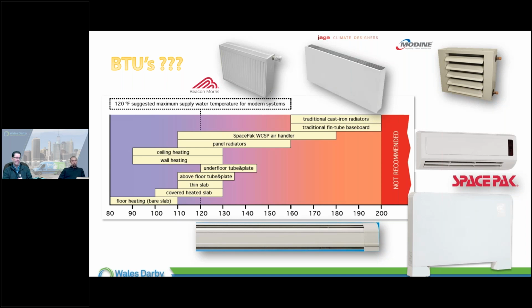So you're causing another series of problems. That's it, you have to play nice, understanding one piece of equipment doing multiple seasons, cooling load and heating load. You have to pick something that maybe doesn't cover all the heating load, so you play nice with the cooling load closer, maybe a little over on heating, but then add an electric boiler, do some other things to reduce the heat load, maybe redo the envelope again.